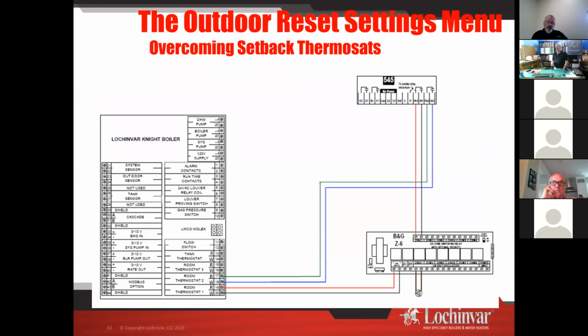Now, where would I use those multiple curves? In settings. This is kind of an example of that. One is overcoming setback thermostats. So people still like to set their temperatures back at night. In the morning it comes on, the boiler's 10 degrees away from set point. We've gotten aggressive with our outdoor reset curve, and they can't bring it up to temperature. And the phone call is, man, my boiler ran for 4 hours and my house still only came up 5 degrees. So the answer sometimes becomes, well, I'm just going to take the outdoor sensor off. So now our night setback thermostats just ruined all of our energy savings.